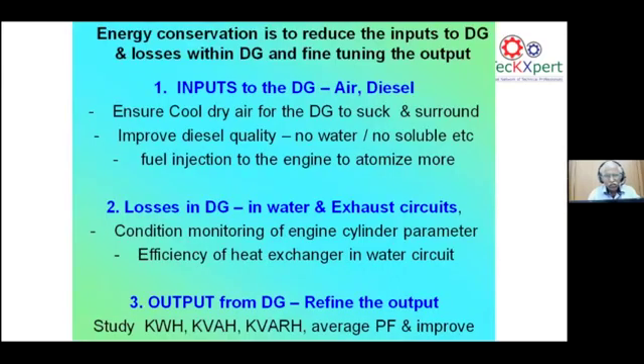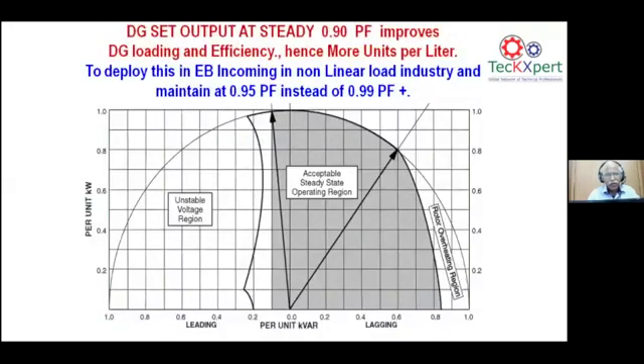Coming to the gensets, some of the gensets are used, so whether we are using the inputs to the genset, air and diesel, everything correctly is to be checked. The losses happening in the water and exhaust circuits, and the output, should be monitored. Here you find why I was telling you on the first slide, on the transformer side, on the electrical distribution side, why you are supposed to keep the power factor around 0.95 to 0.96 for stable function. The acceptable steady state operating region for a genset is almost from 1 to 0.8.